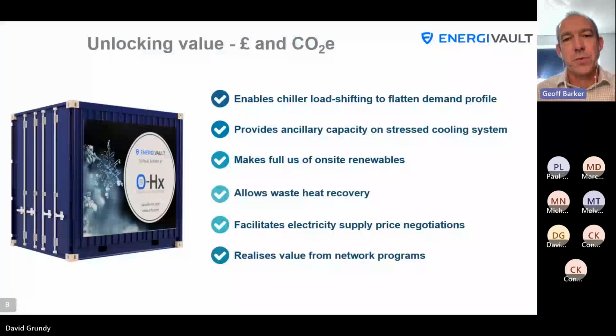Okay. What we've found talking to a lot of potential clients is carbon saving is actually one of the main drivers, but obviously energy saving and cost saving, particularly over the recent past with energy costs being so high, is not surprisingly equally important. Just to explain a little bit about where CO2 savings come from. One of the main applications for EnergiVault is the optimization of existing chillers. Chillers on part load are generally not operating as efficiently as they are on full load, and depending on how you set the controls up, effectively you can avoid that, depending on how many chillers there are and whether they're cascaded or whatever.